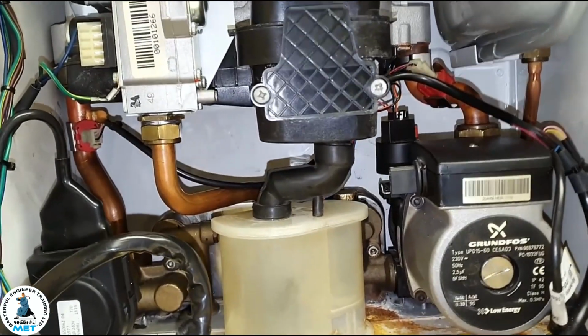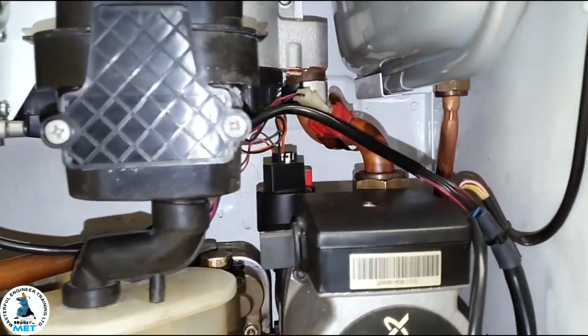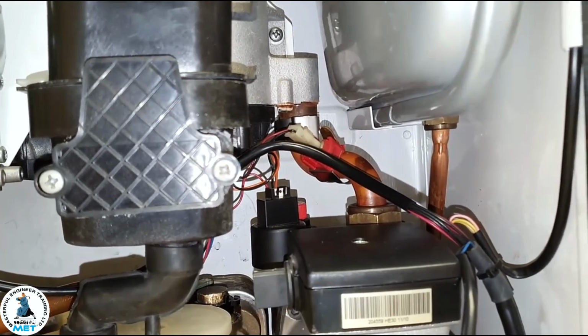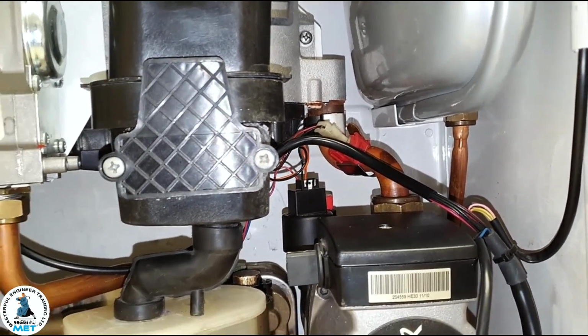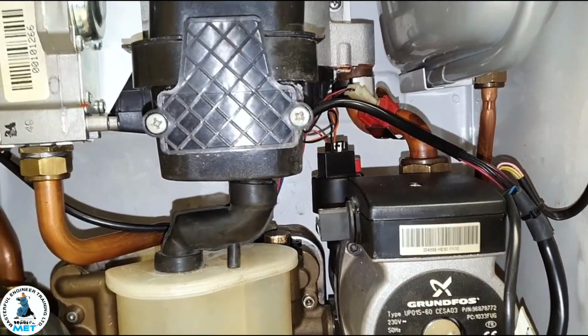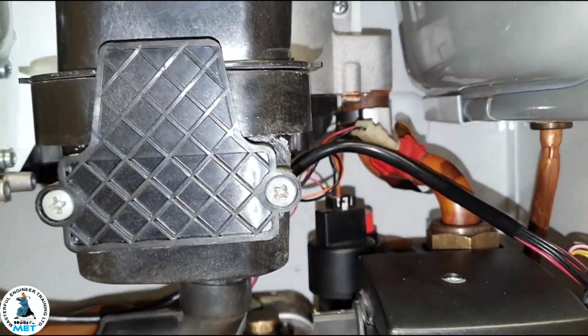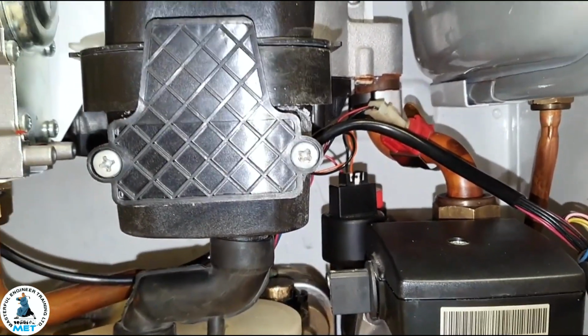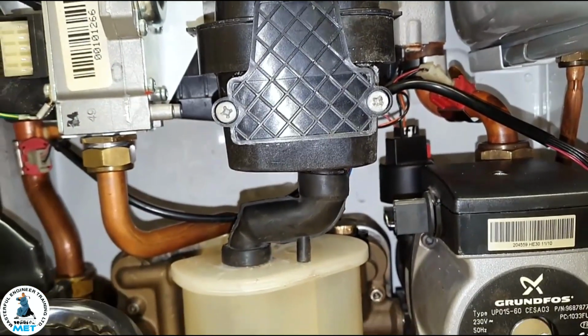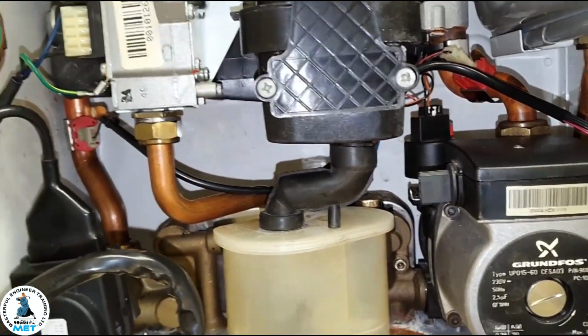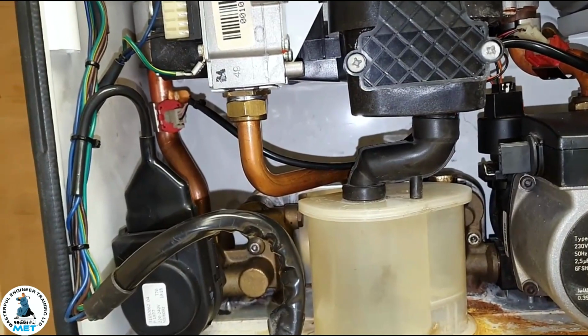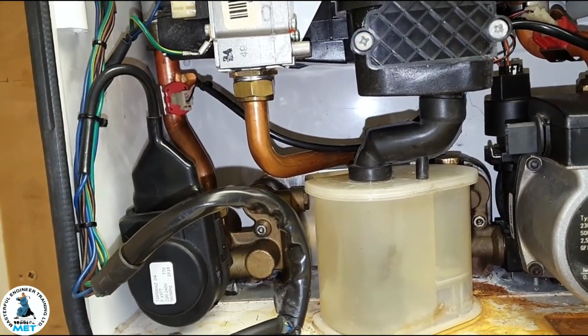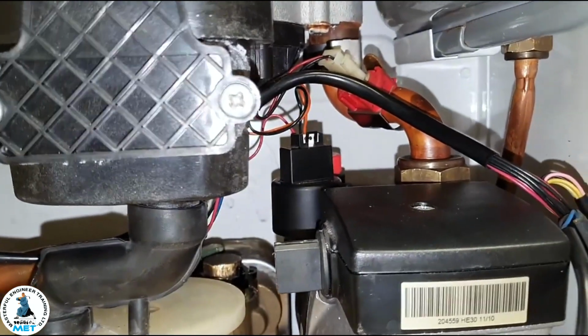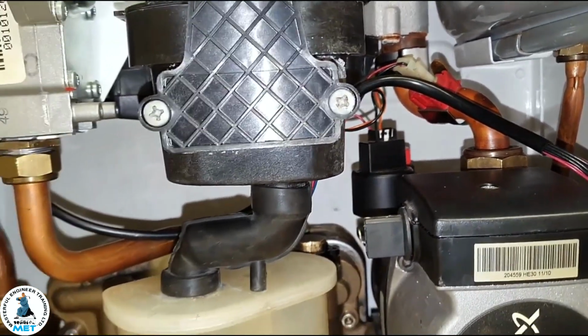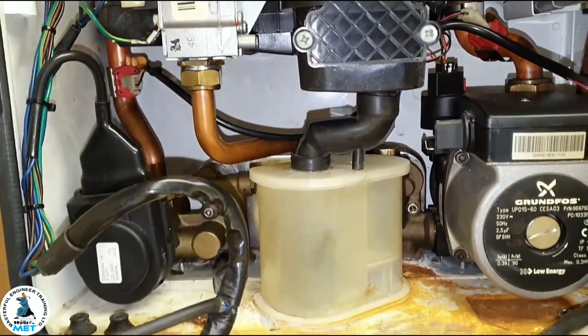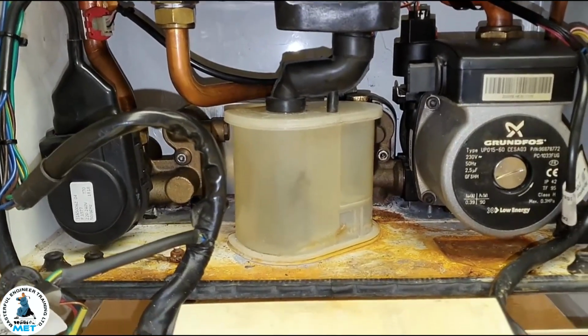Because over time, if this pipe is blocked, it's going to cause the system to over-pressurize and open the PRV. The PRV will let water out, so when the system cools and contracts, the pressure is going to go down. The pressure on the gauge will be down and the customer will see it. Then the pressure sensor will detect it and that code will come on. So it's a knock-on effect on the whole thing. Does that make it clear? Yeah.